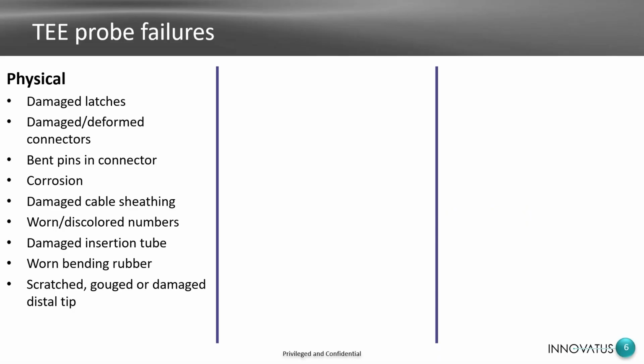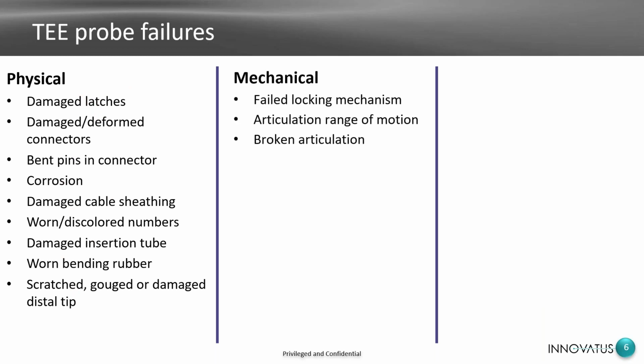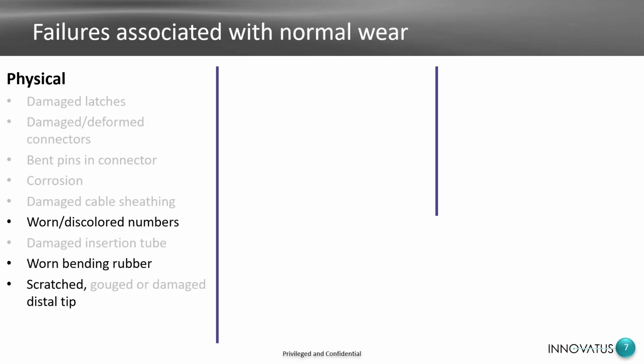So let's look at the different types of TEE probe failures. First and foremost, we have physical, where we have different types of damage. Some of these are not so bad, and some of these are borderline catastrophic. I'm not going to go through this line by line, but we have all these different types of damages that can occur to a TEE probe. And then we have mechanical. And then lastly, we have electrical failures. Now, these are the failures that are associated with normal wear. TEE probes do fail due to normal wear and tear. It's just not that often. Typically, when we get a probe in, it is due to something that was preventable.